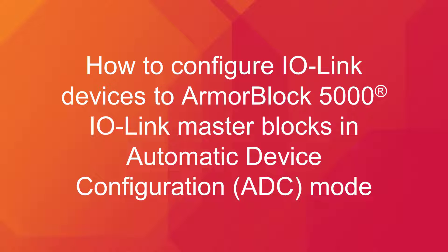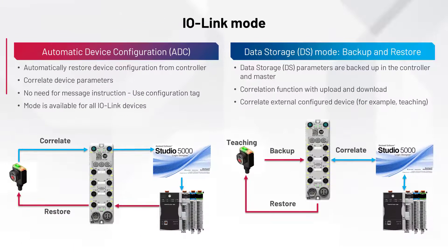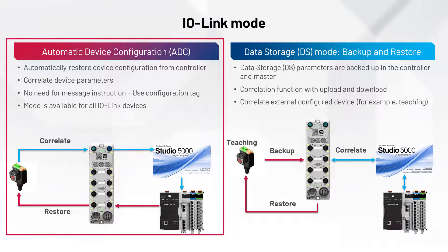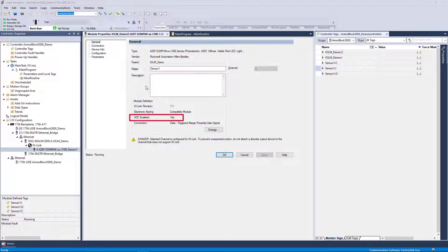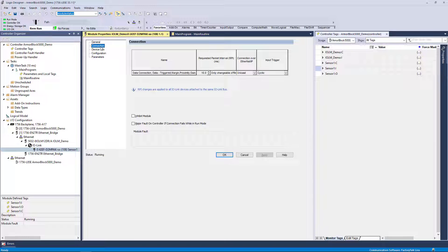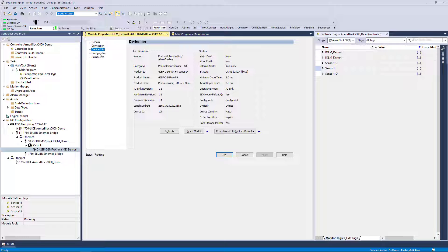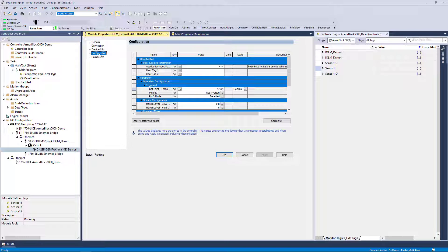This video demonstrates how to configure IO-Link devices to an Armor Block 5000 IO-Link master block when using Automatic Device Configuration, or ADC mode. This mode is intended to be used when the controller is the primary handler of the configuration. Choosing Yes to ADC enabled within the IO-Link device add-on profile will allow a device to utilize ADC mode. For an IO-Link device connected to an Armor Block 5000 IO-Link master, you can view connection and device information as well as gain access to the configuration and parameters of the device.